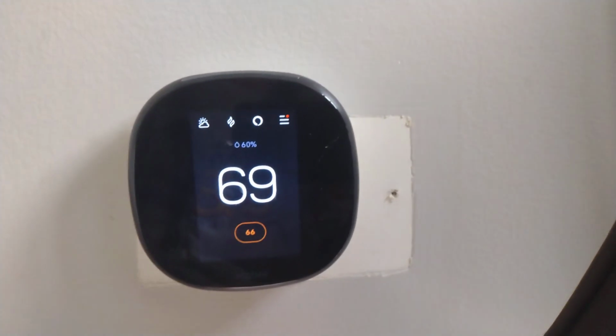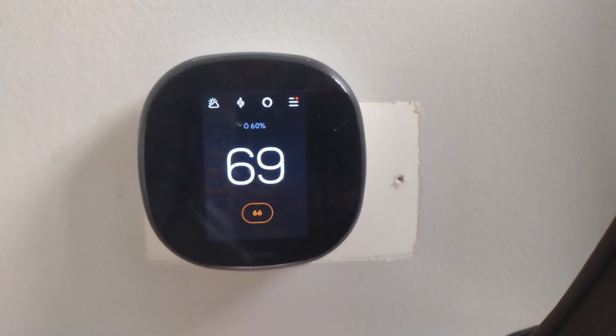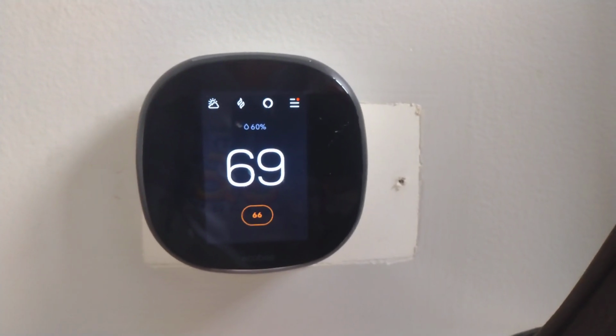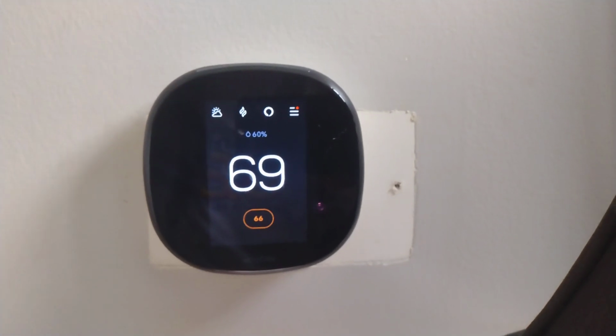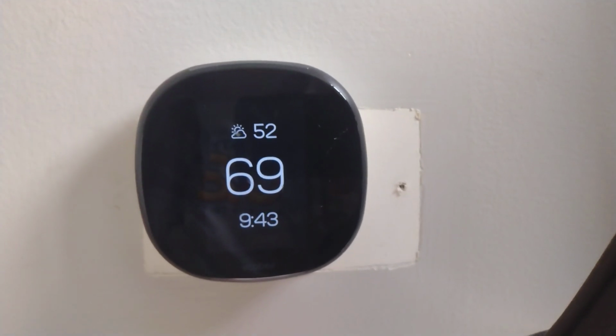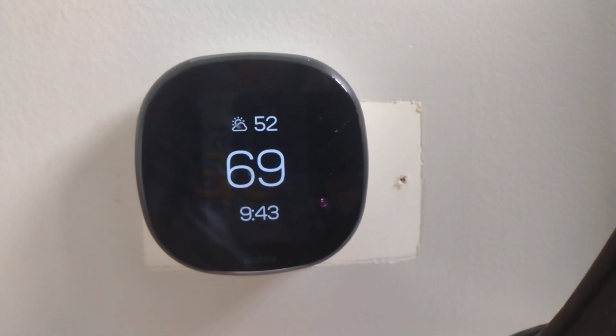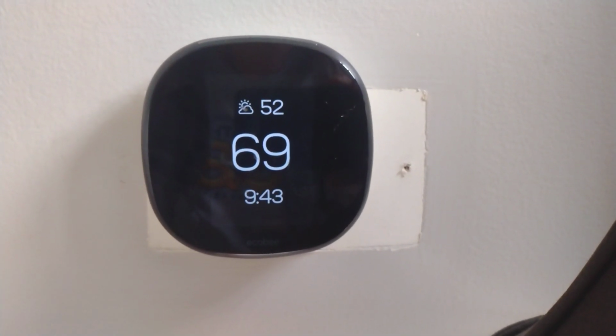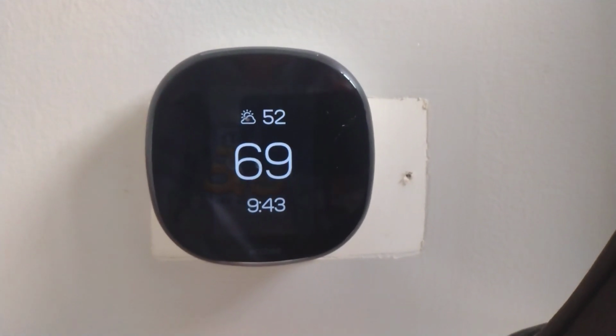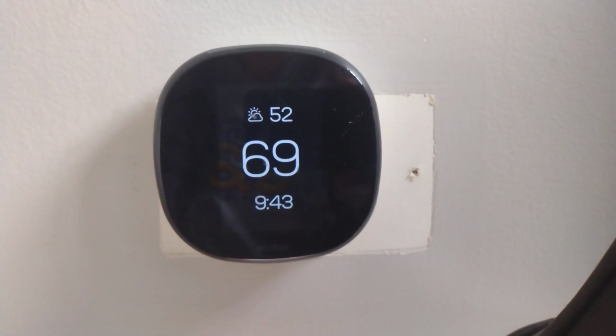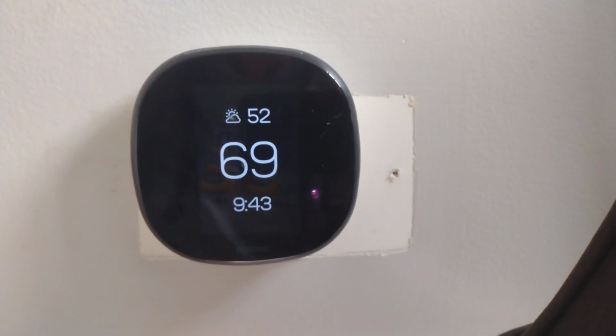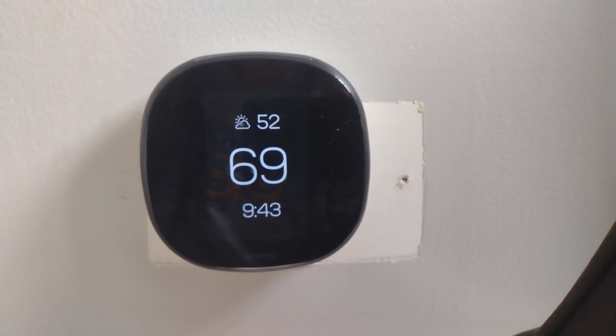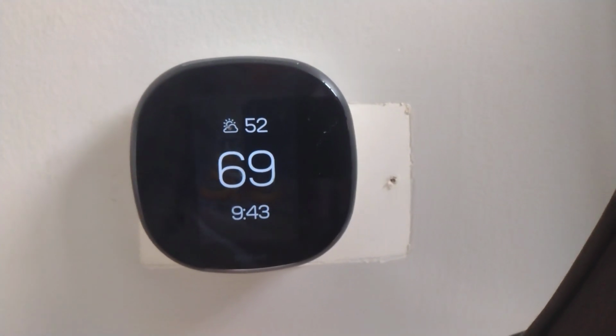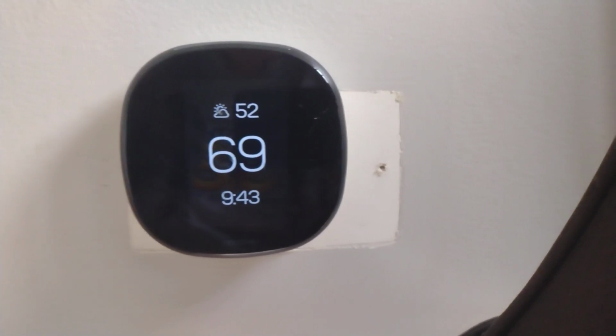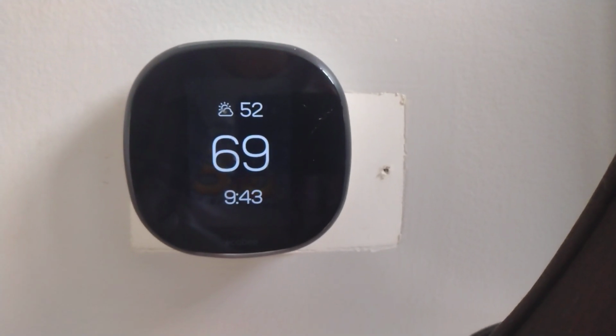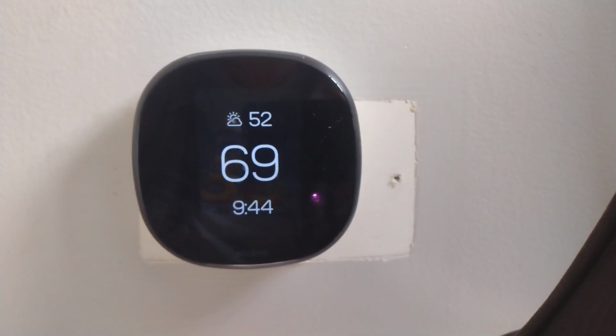Sometimes that could happen because of a power surge or some other event. But in our case, the Ecobee was drawing so much power through the low voltage transformer that eventually it caused it to fail. So we had to replace them. And Ecobee doesn't tell their customers that this is a possible problem, but it does draw a lot more power from the transformer than it would without the thermostat. So it's a common problem. I would bet that it's fairly widespread. I saw a number of people asking the same type of questions online about the intermittent power.